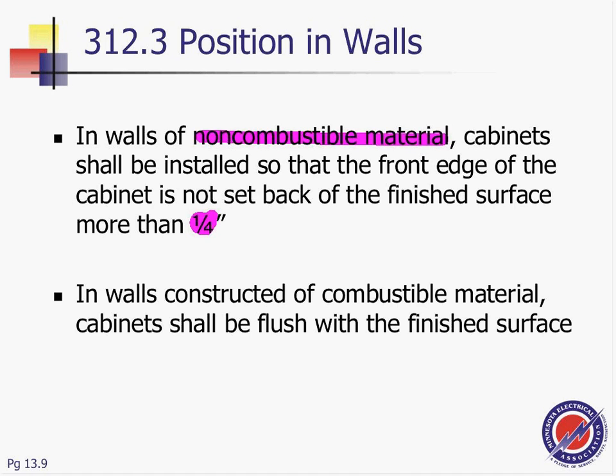of the cabinet is not set back from the surface more than 1/4 inch. So you don't want it to be set back more than 1/4 inch if it's non-combustible. If it's combustible, like wood, it has to be flush with the surface. And that has to do, guys, with fire and the spread of fire. In combustible material, if there's any arc or spark inside the enclosure, you want it to be completely enclosed so it doesn't spread to the combustible material. If it's non-combustible like concrete, 1/4 inch, because if it burns the concrete, there's nothing to burn. So very interesting: 1/4 inch for concrete, non-combustible, and flush for wood, combustible. Anything else about that?